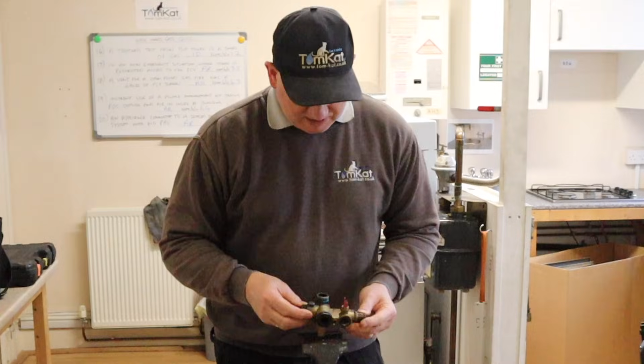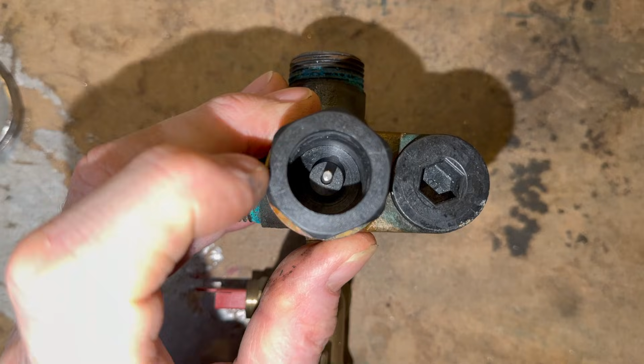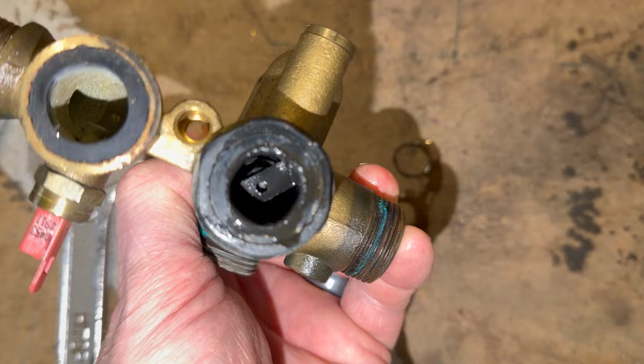First part we're going to look at is this left side of the hydro block, or the diverter valve. If we look down in here, this is always a telltale sign if the seals have gone. But it isn't, it's really clean inside there, and it pushes down really easily. So we're going to strip it and see what it's like inside.